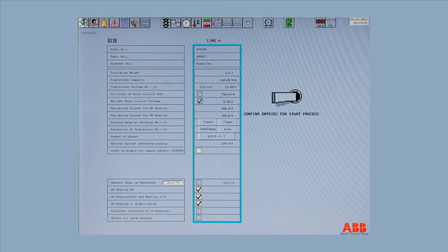These values must be independently and carefully checked by a second person. When doing the checking, assume that there is an error until you prove to yourself that they are correct. Remember that windings can be made from either copper or aluminum. A wrong entry in this column will invalidate the relationship between winding temperature and winding resistance. This could cause damage to the transformer during the heating steps of the process.